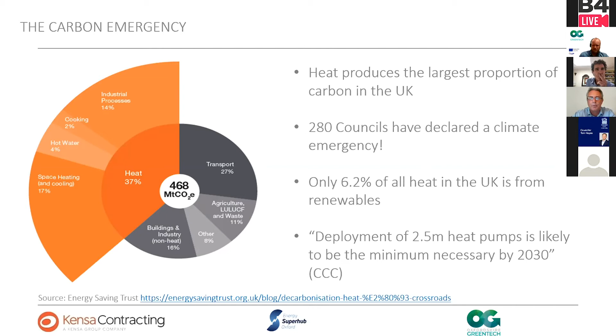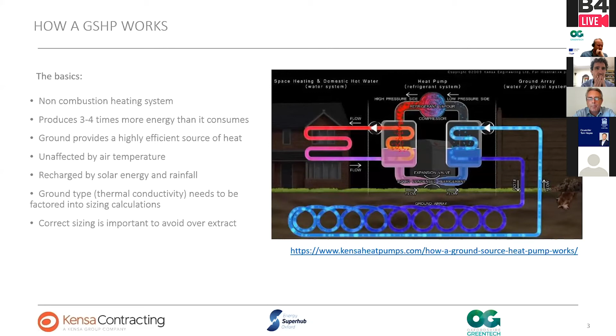Very quickly, what are they? I've put a link there to a more detailed explanation. But essentially, they're an electrically driven device that extracts heat from the environment. In the ground source case, it takes loads of very low grade heat, between 2 and 8 Celsius, compresses it, ups the temperature, and delivers it into homes at somewhere between 45 and 60 degrees. The really cool thing is the amount of heat you get out is much higher than the amount of electricity it takes to run it, typically 3 to 4 times. That's why they end up being a very low carbon heat source.